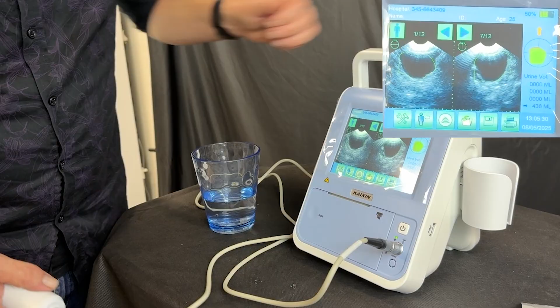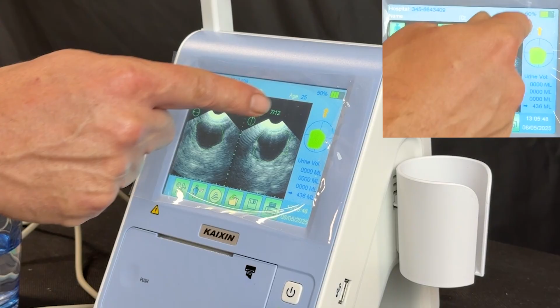Okay. So we can see here residual volume of 436 mils. That's quite a lot. That's okay. And you can see here also the accuracy of the scan. We kind of want to be in the center of that crosshair. Could have done a little bit better here. The software is telling you could have angled that probe up a little bit. That's not too bad though.